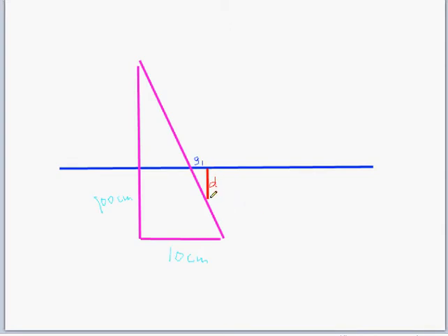So this is our depth D, here's G1, this little gap, and from here down to here is 100 centimeters, that's our isocenter. And because our jaw setting on this part of the beam is 10 centimeters, so the lower jaw setting is 10 cm, that is defined at isocenter.